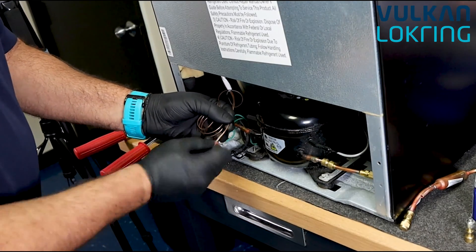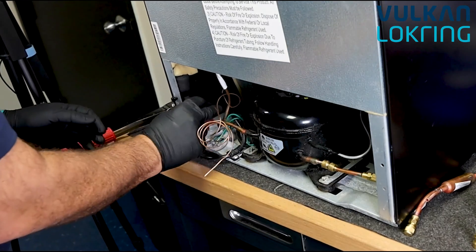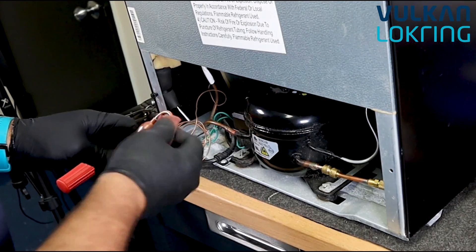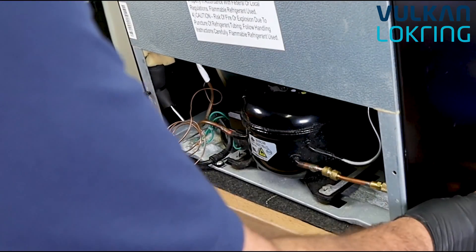Thank you everyone for joining us today. Today we'll demonstrate the installation of a standard refrigerant dryer using the Lokring joining system. Charlie is cleaning the capillary tube, then transitioning to cleaning the heat loop, and next he'll be cleaning the dryer itself. Preparation for Lokring connections is just like brazing — we need to ensure that both sides of the tubes are clean and free from oxidation or contamination prior to assembly.